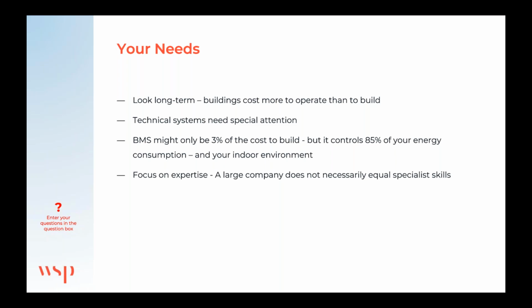So your needs, what are they? They could be very different from building owner to building owner, but it's probably a good idea to look long term, because buildings cost more to operate than they cost to build. The technical system needs special attention. In the old times, construction was the biggest expense when building a new building. Today the technical systems are around half of the cost of building, but they're very important for operation. The building management system normally costs between 1.5% to 3% of the total building cost, but it controls 85% of your energy consumption and your indoor climate. So it's very, very important.